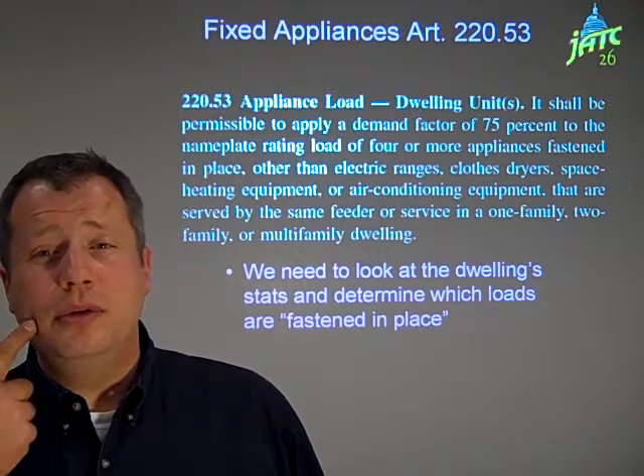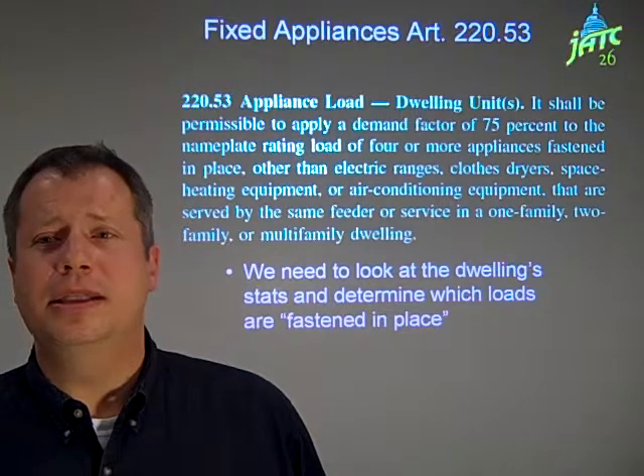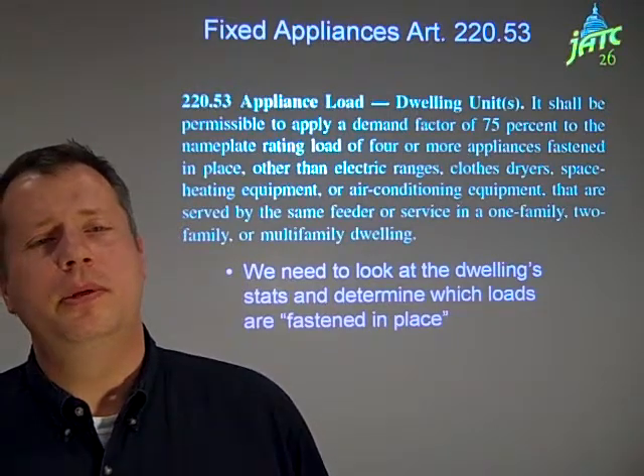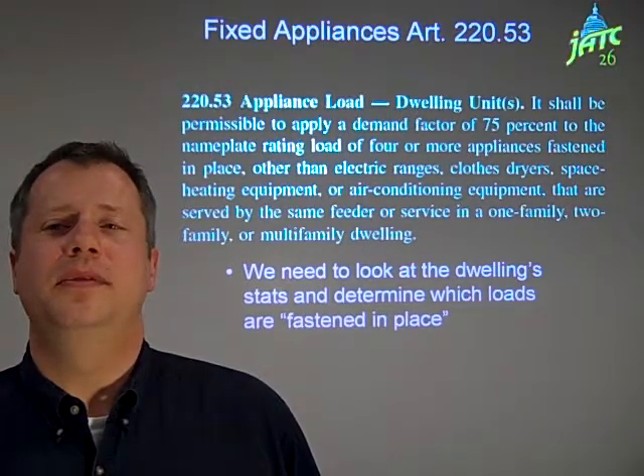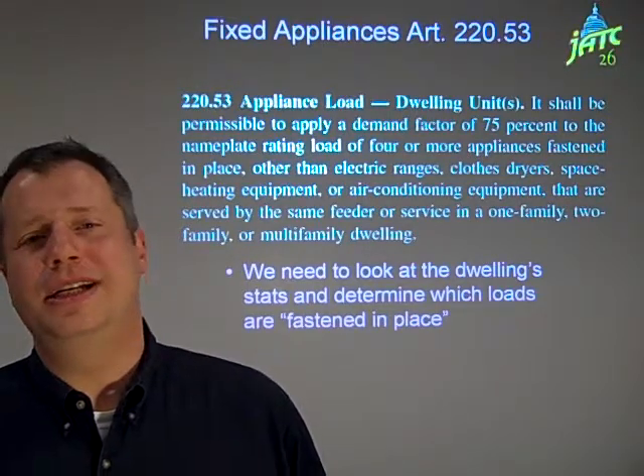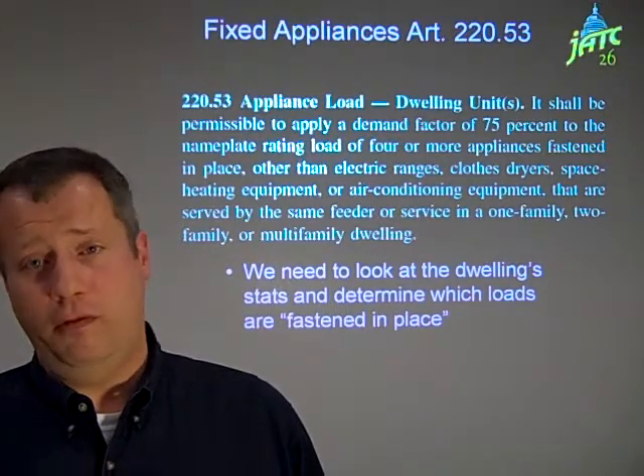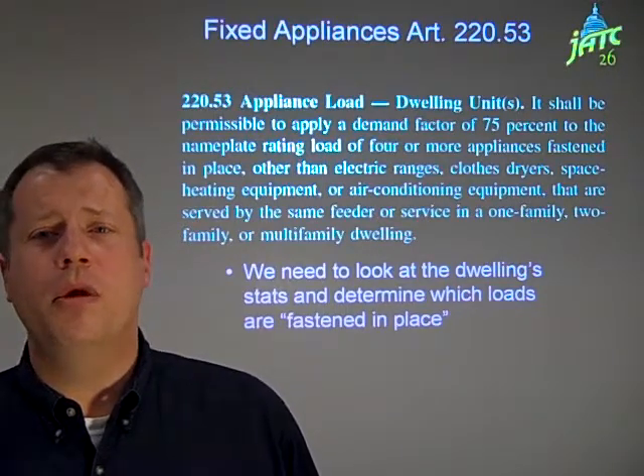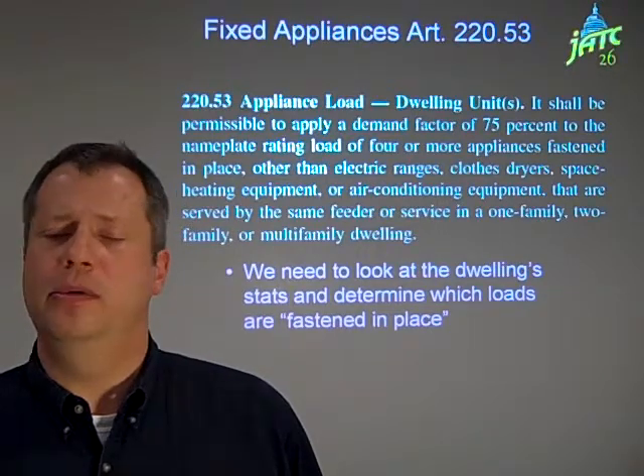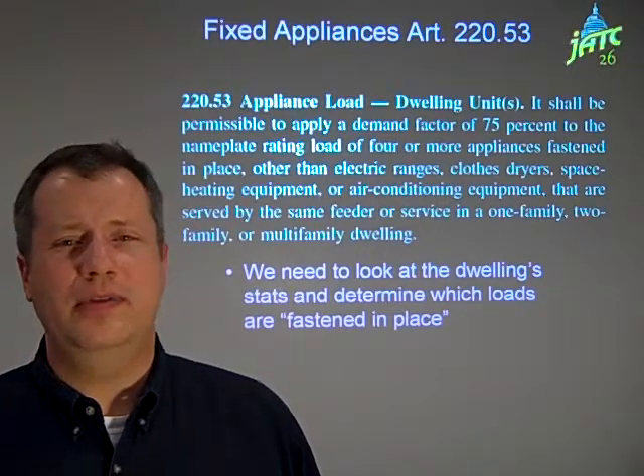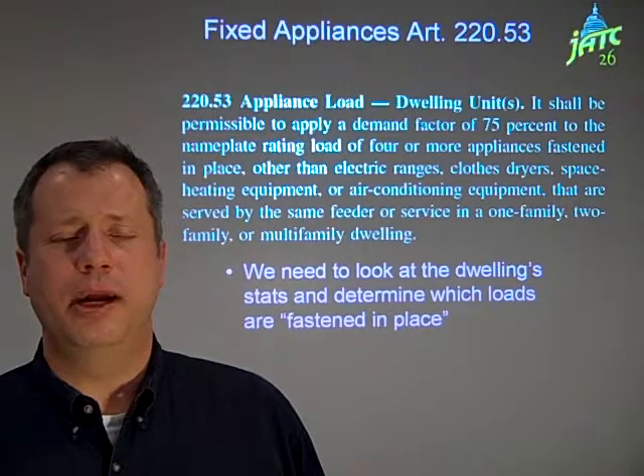Looking at Article 220.53, it states that it shall be permissible to apply a demand factor of 75% to the nameplate rating load of four or more appliances fastened in place — so we're not talking about things that get plugged in and moved around the house.